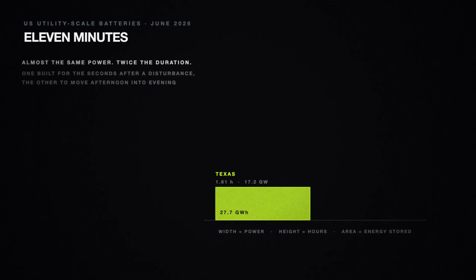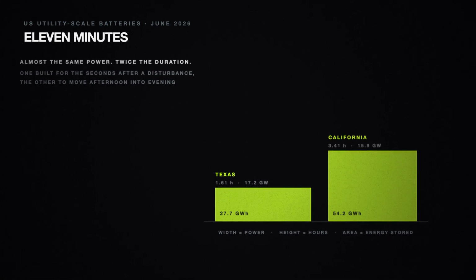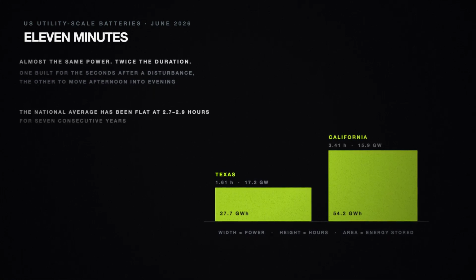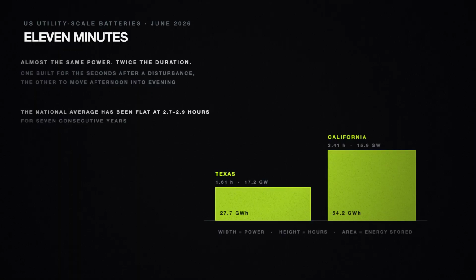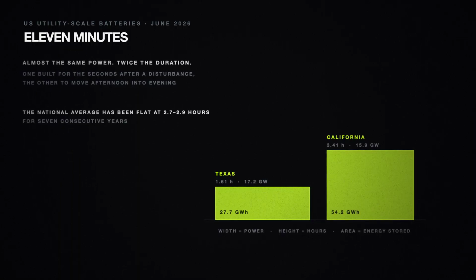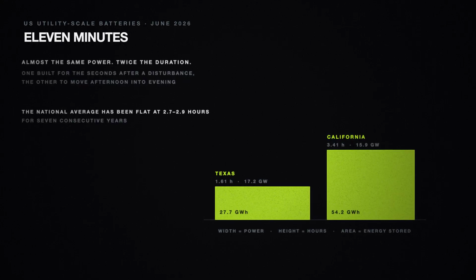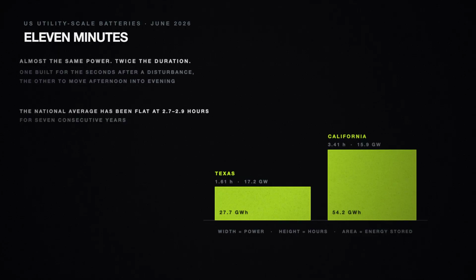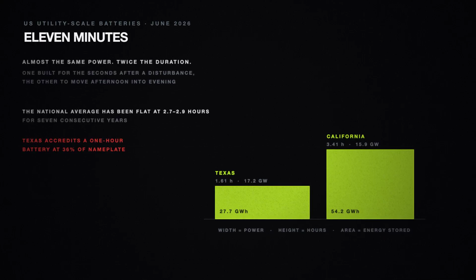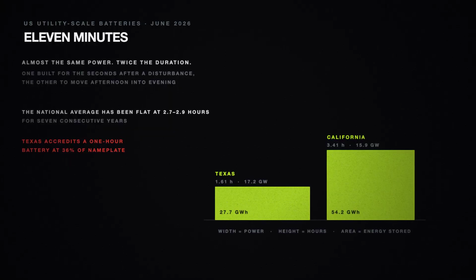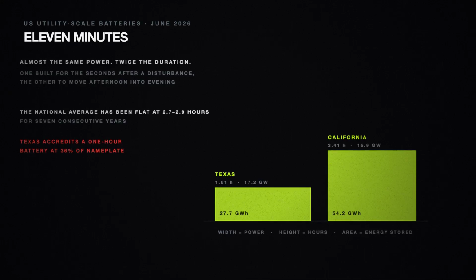Texas built a fleet averaging 1.6 hours for fast response in the seconds after a disturbance. California built one averaging 3.4 to move energy from afternoon to evening. 2 different machines, 2 different jobs, 1 misleading national number. And the Texas grid operator, accrediting what it can count on at peak, gives a battery of 1 hour or less 36% credit for its nameplate.